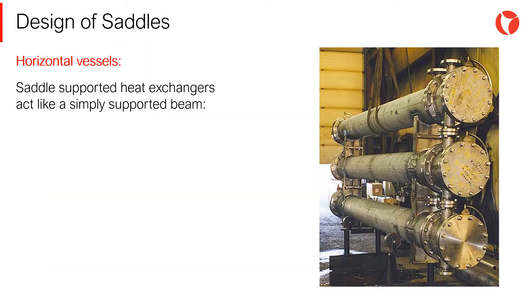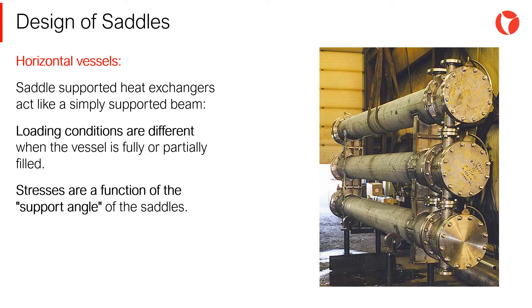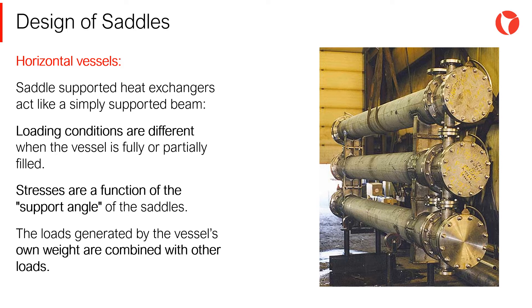A horizontal pressure vessel supported on saddles acts like a simply supported beam with the following considerations. Loading conditions are different when the vessel is fully or partially filled. Stresses are a function of the support angle of the saddles. The loads generated by the vessel's own weight are combined with other loads.